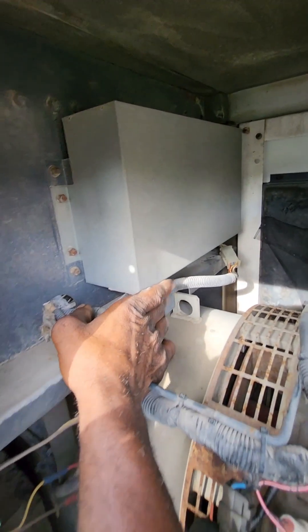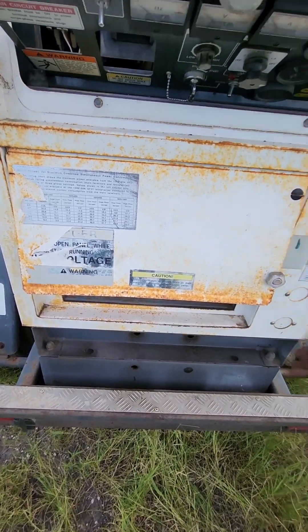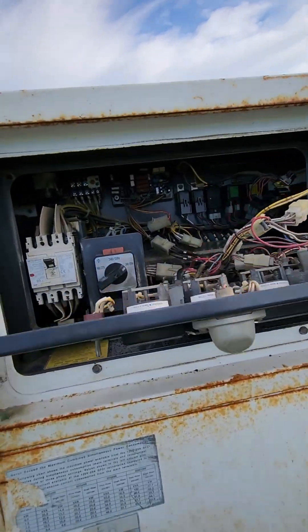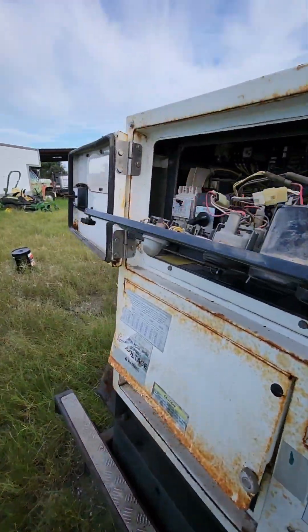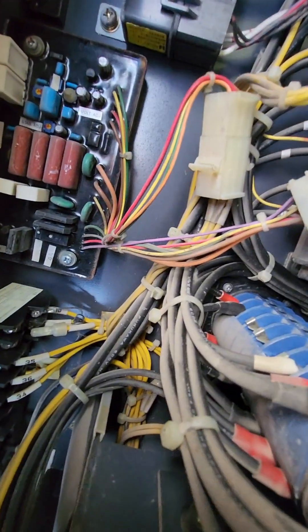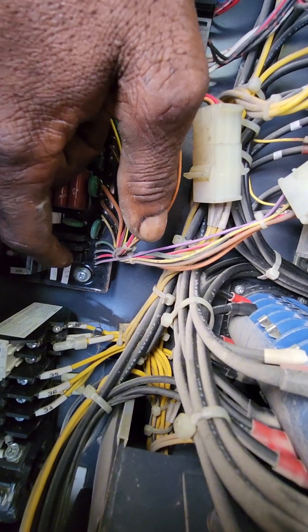Well, I think this is going to be a fast one. I was looking for cut wires; I smelled for a burn — when something's burned you can usually smell a pungent smell — but I did not get any pungent burn smell. I tested the relays, the relays are all good, and the breakers — everything seemed to be good.